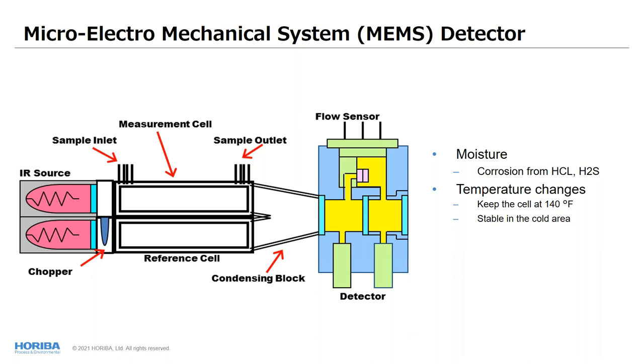Here is how NDIR works. The sample gas flows in and out of the sample cell, and IR light alternately radiates through the sample cell and the sealed reference cell, controlled by a chopper. The gas being measured absorbs IR energy in the sample cell, and it reduces the pressure in the detector gas chamber. Because of this change of pressure, the detector gas flows from one chamber to the second chamber. The amount of flow is proportional to the gas concentration. We look at how the detector condition is changing. And the compensating detector measures only the interference gas on the other side, so the interference compensation is made properly.